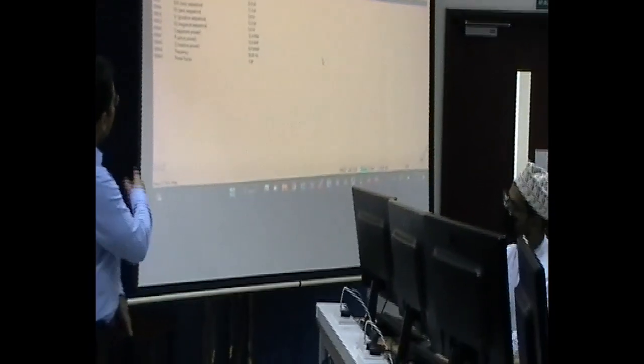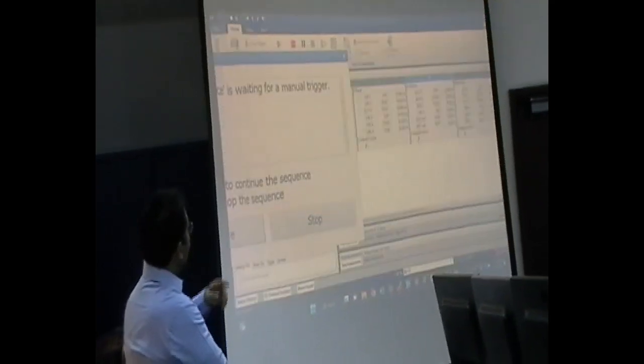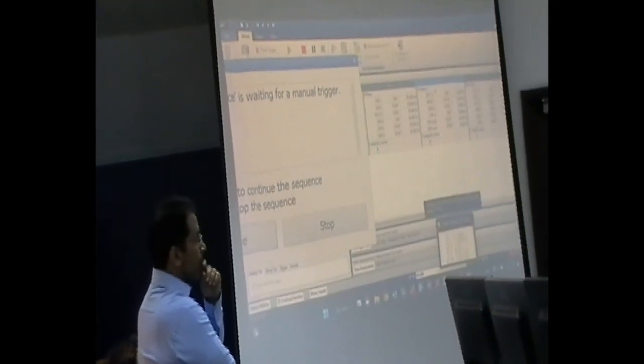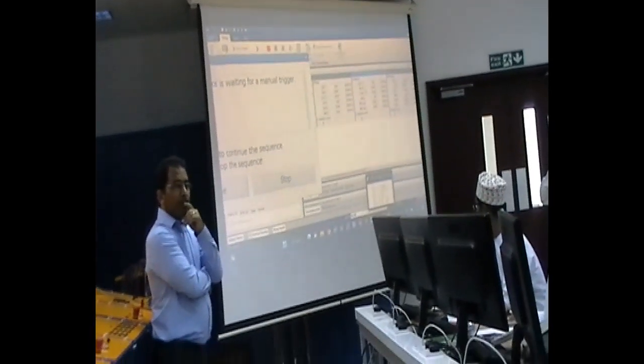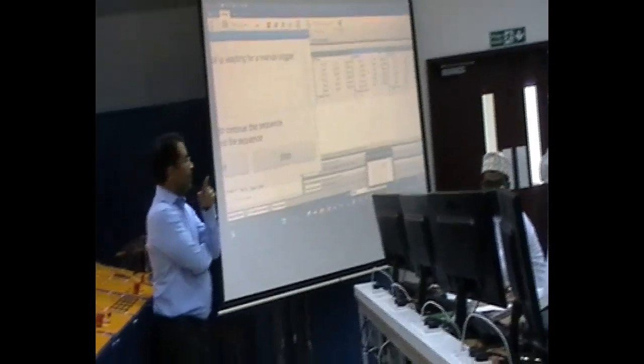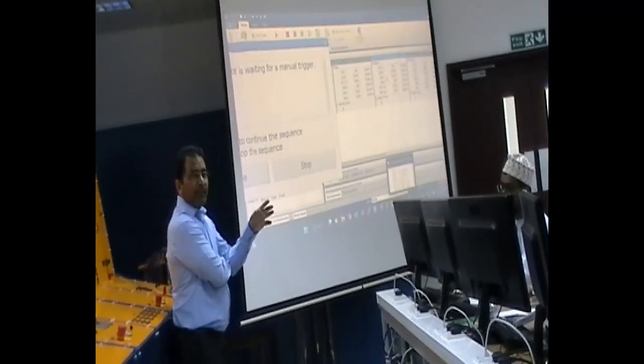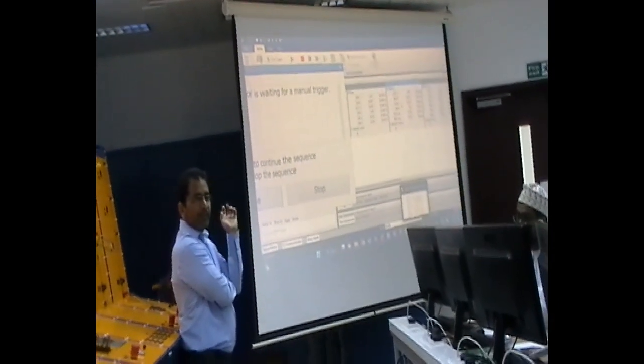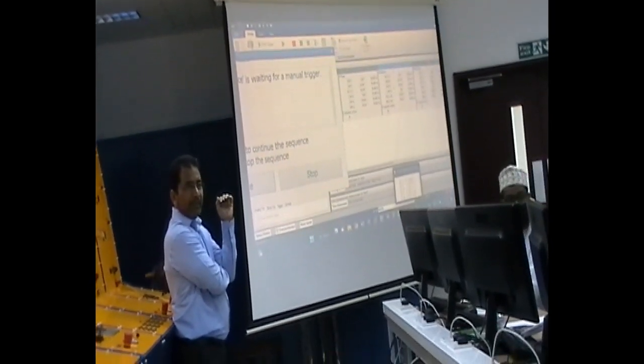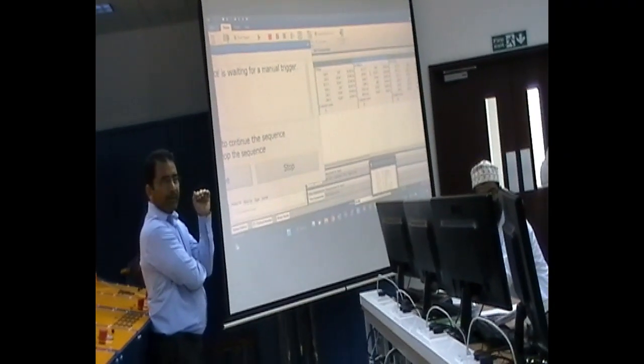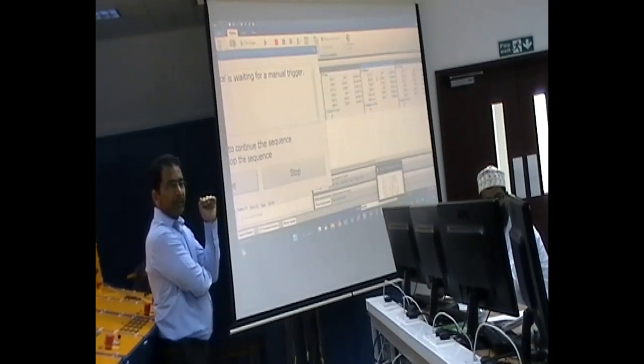Before that, I'm injecting different values, unbalanced values in all three phases. What's appearing in the relay is 400 because we've injected 1 ampere in the red. Here we are injecting test number 4. I'm injecting 63.5 volts in the red, 40 in the yellow, and 20 in the blue. A student asks, is this measured quantities here or injected? It's injected from the test kit and measured in the relay.